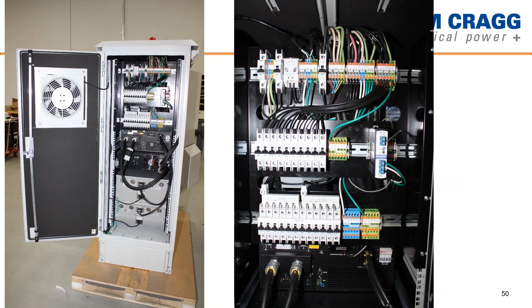So we included all of the engineering for all of this on the front side, got the design approved, and then worked with a couple of different manufacturers to supply the complete solution. As you can see, there's quite a bit of distribution they required for this project. There's a lot of back and forth between transformers, creating the 120 in to 240 to 120 out. So we have multiple voltages available on the output as well. We've split it through the system.